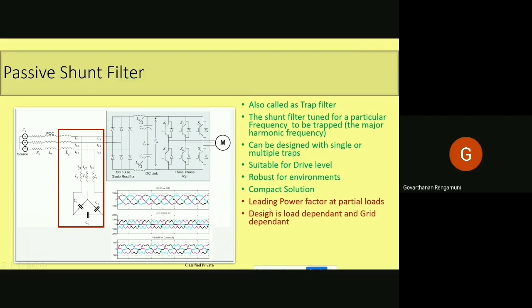And there are some disadvantages, like leading power factor at partial loads, and the design is load dependent because the tuning should be done for the filters considering the available LC component inside the drive. So we need to understand the drive and we need to tune this filter L and C values.